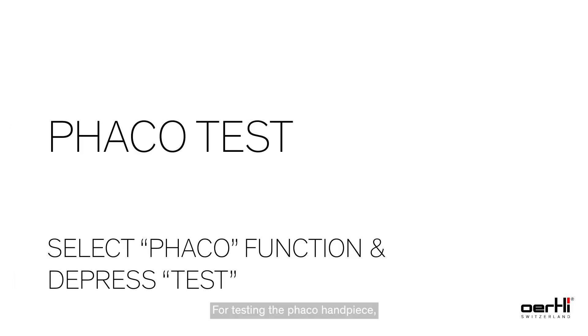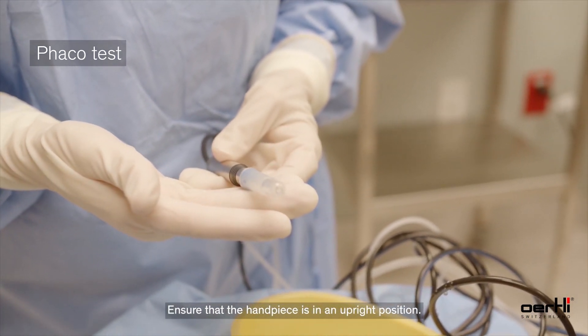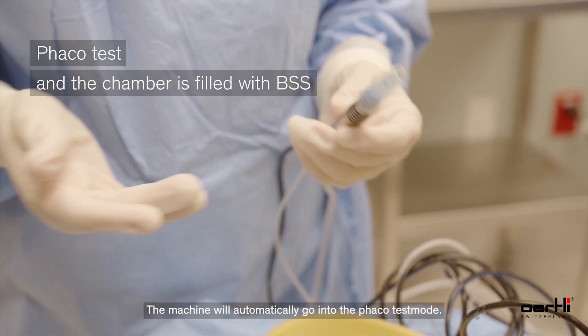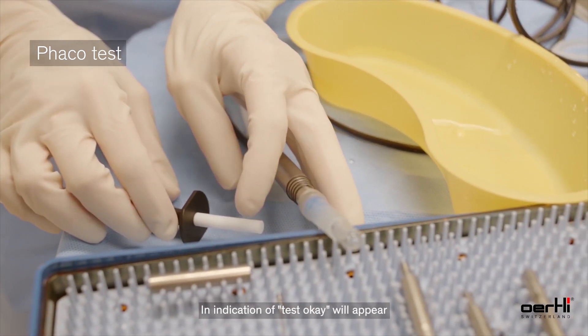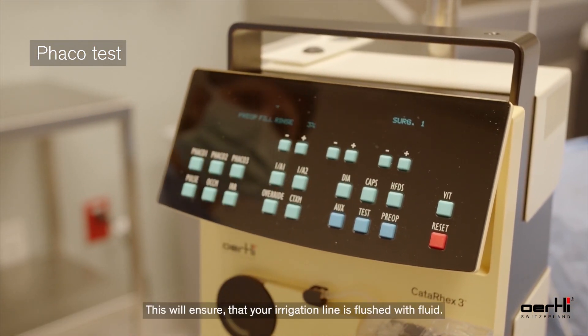For testing the Phaco handpiece, ensure the test chamber is securely on the Phaco handpiece and that the handpiece is in an upright position. The machine will automatically go into Phaco test mode. An indication of test okay will appear on the screen if everything runs according to the machine's parameters.